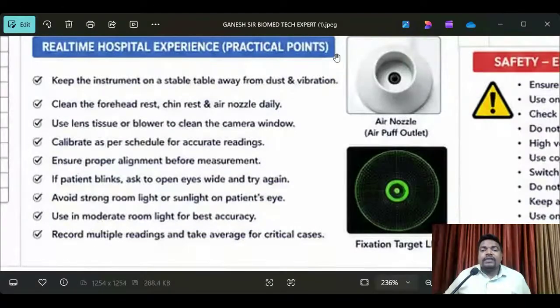Now, real-time hospital experience practice points. Listen carefully. Keep the instrument on a stable table away from dust and vibrations. Clean the forehead rest, chin rest and air nozzle daily. Use a lens tissue or blower to clean the camera window. Next, calibrate as per schedule for accurate readings, and ensure proper alignment before measurement. If the patient blinks, ask them to open their eyes wide and try again. Avoid strong room light or sunlight on the patient's eye. Use moderate room light for best accuracy, and record multiple readings and take the average for critical cases.